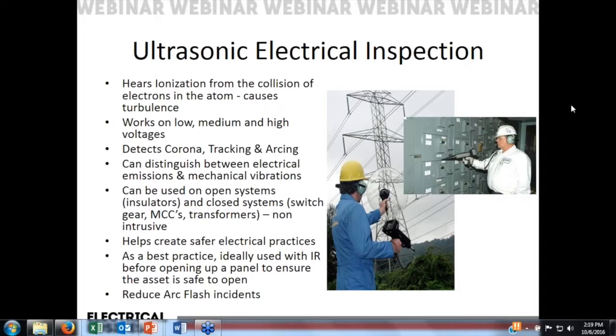And again, the name of the game here is that it's non-intrusive. We are not placing any part of the instrument inside an electrical asset, panel, or anything. We are away from it at safe distances, which helps us create a safer electrical practice, as you can see here. It reduces arc flash and shock hazards as well, and can be used as a best practice with infrared. Before opening up a panel, maybe we're trying to do an infrared scan, but we want to make sure that panel is safe to open up. We can do an ultrasonic scan to determine if there's anything going on behind that panel or not, and if there isn't, then we can safely open it up for infrared as you get your PPE on.